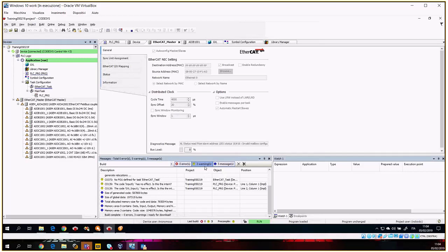I don't know if it works because of Ethercat through our switch. Usually you should also be able to run Ethercat on standard Ethernet, but it's not mandatory. I recommend, I suggest you have a peer-to-peer connection between the LAN and the device, because using a switch sometimes it is not possible to execute a communication on Ethercat.